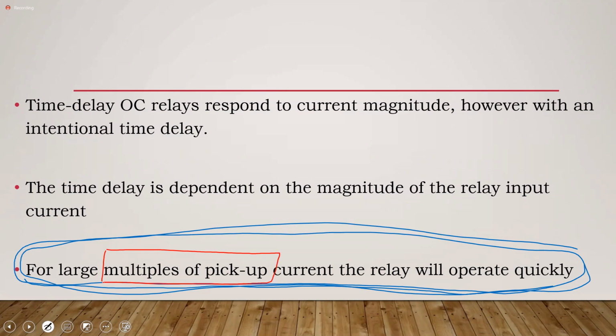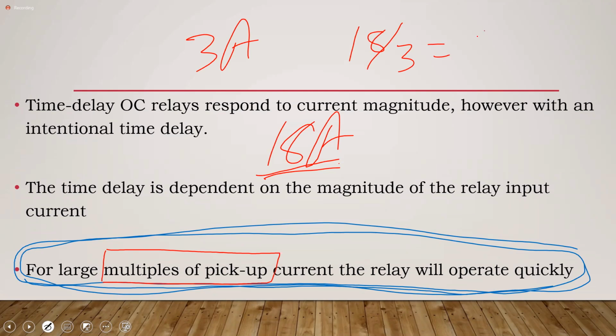Multiples of pickup. So in other words, if the pickup current is 3 amperes, in terms of the operation of the relay, if a current of 18 amperes comes into the relay, it will be 18 divided by 3 to give you 6. And this is a 6. This 6 represents multiples of pickup. I'll show you that in a few minutes. Just take this from now. So it operates based on multiples of pickup current. Are we clear?